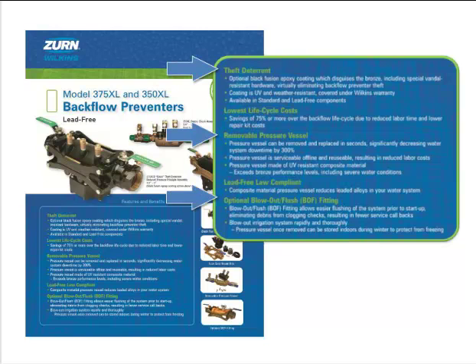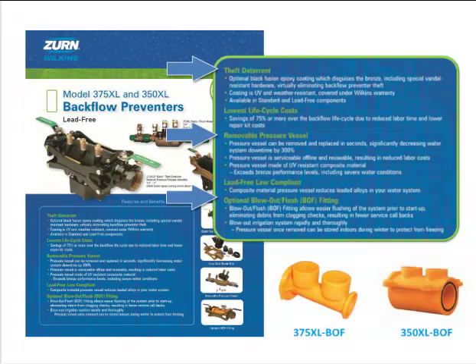Zurn Wilkins has also created a new option for the 350s and 375s: a blowout flush fitting. The blowout flush fitting provides a quick and easy way to protect your backflow preventers in the winter from freezing. In the fall, simply remove the pressure vessel and install the blowout flush fitting. Then hook up an air compressor and blow out the system, evacuating all the water out of the system to protect your system from freezing. Afterwards, leave the fitting in place for the winter.